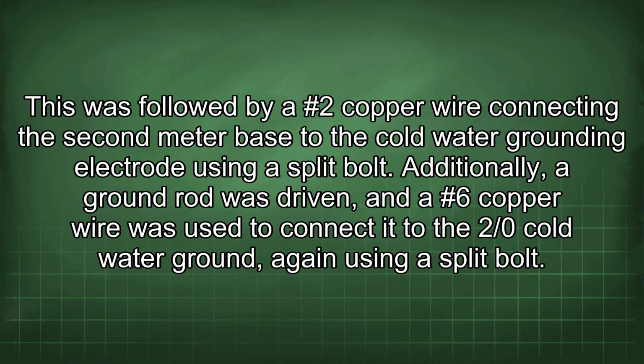This was followed by a #2 copper wire connecting the second meter base to the cold water grounding electrode using a split bolt. Additionally, a ground rod was driven and a #6 copper wire was used to connect it to the 2/0 cold water ground, again using a split bolt.